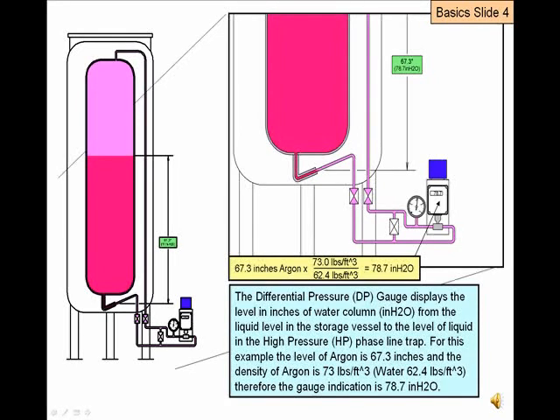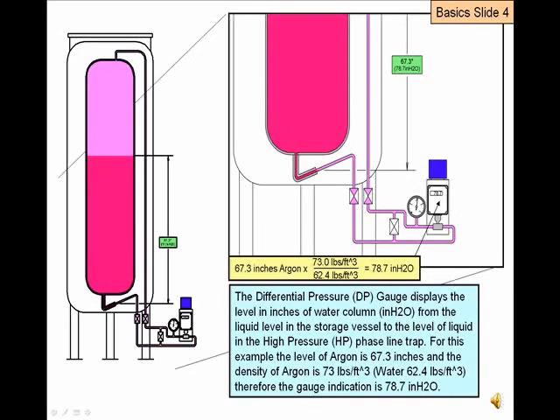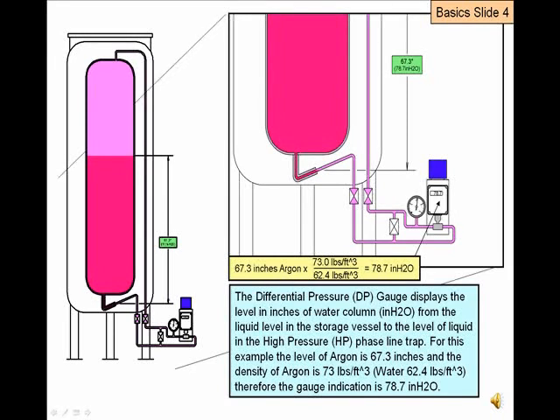Argon is about 17% heavier than water, and therefore the gauge reads 78.7 inches of water. The gas in the top of the tank will add to the total differential pressure, but has been ignored in this example to simplify the explanation.